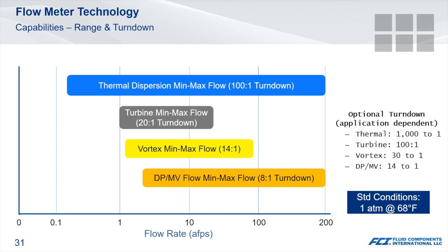As the graph illustrates, there is a significant difference between the more common technologies used. The standard turndown ratio of thermal often exceeds the optional turndown capabilities of technologies such as vortex and differential pressure multivariable transmitters. There are also differences in the flow velocity that a given technology can measure. Some are better at lower and higher flow rates than others. Some are also dependent upon variables such as gas density or Reynolds numbers. It is important to understand the limitations of a technology for any given application.